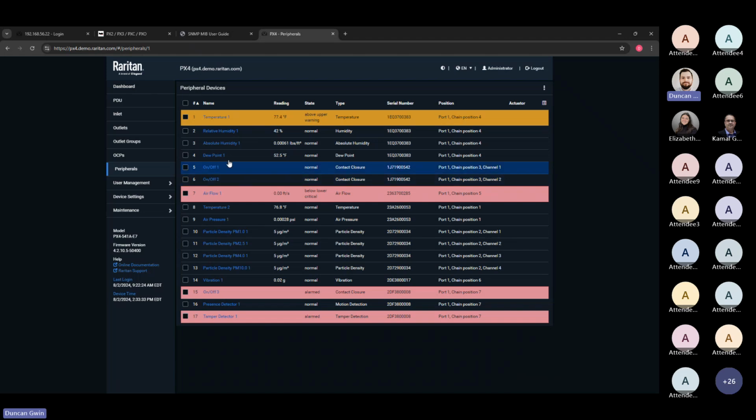So, in a data center environment, you'll see oftentimes that things are standardized, and you'll connect the temperature sensor first and then the contact closure, or whatever sensors you're chaining together. They will follow a typical build, in which case you should have very similar IDs. But you may have a case where maybe they weren't installed in the same direction or order, and things got reordered, and now you have different sensor IDs.